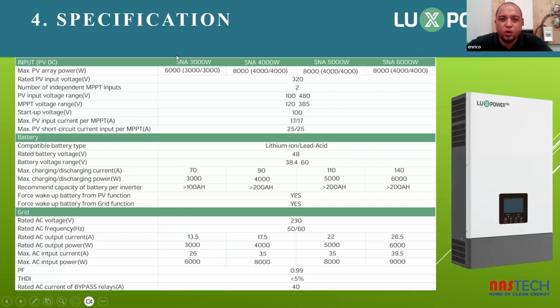Specifications of the SNA 5 kilowatt. So the SNA 5 kilowatt, this is new specifications. There are two versions of the SNA 5 kilowatt. There is the older version with the red dip switches and a newer version with the blue dip switches. But this version is the data that's on the website at the moment. It's more closely spec'd to the SNA 6 kilowatt that we're looking forward to getting in future. But the main specs still remain the same.